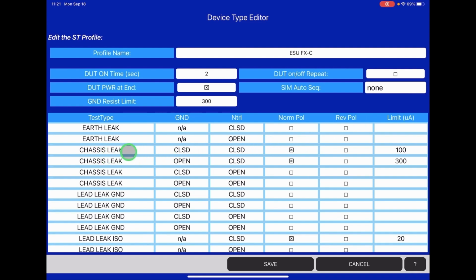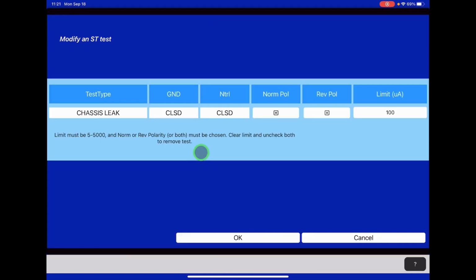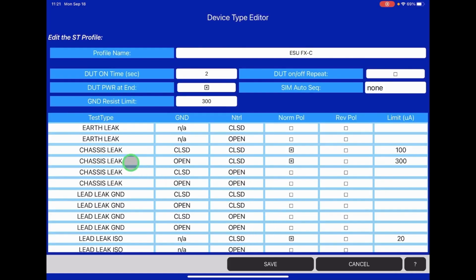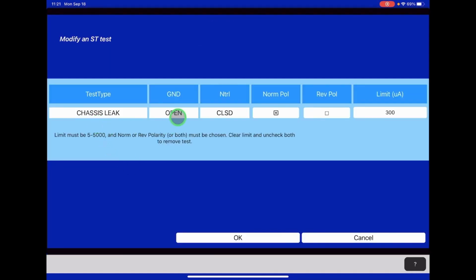So this device requires us to do an earth leakage test or a chassis leakage test. We went ahead and programmed the chassis leakage test in what they call normal conditions, which is the ground closed, the neutral closed. In normal polarity is required to be done, and it's got a leakage limit of 100. So that's been programmed. We also need to do this same chassis leakage test, but with the ground open, or what's called a single fault condition, neutral closed. And we're going to do this again in normal polarity only, and the limit is 300 microamps.